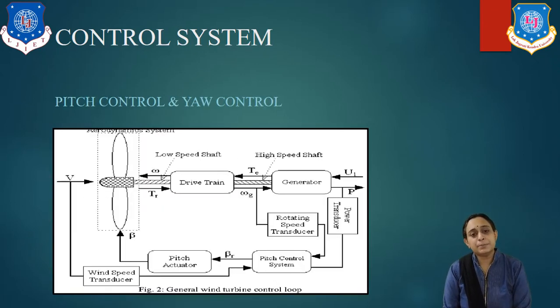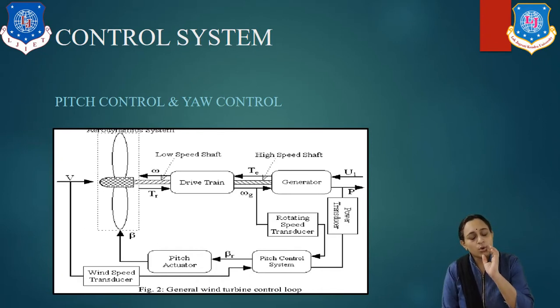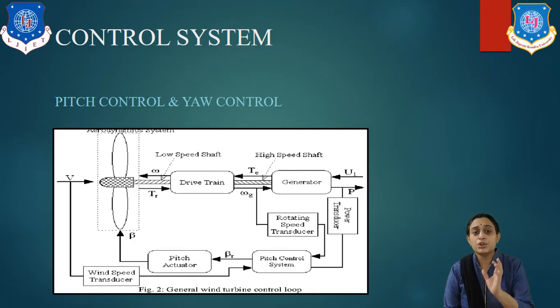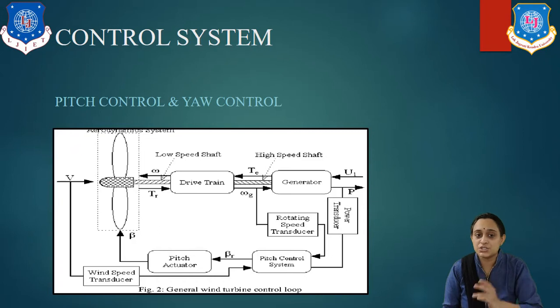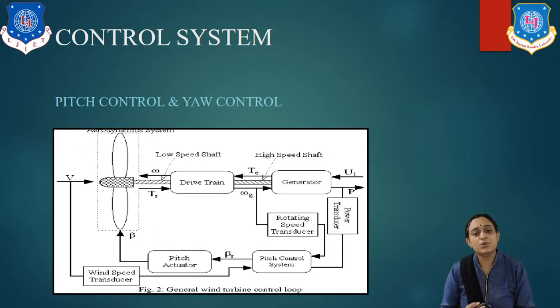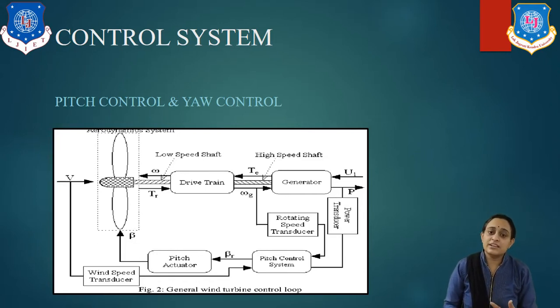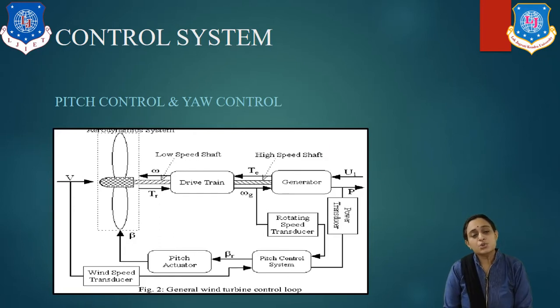Let us understand the pitch control or control system. It automatically changes the rotor blade angle and controls rotor RPM. The blades are provided with hydraulic pitch control. The pitch angle can be controlled in a wide range of 0 to 30 degrees to obtain the desired power velocity.